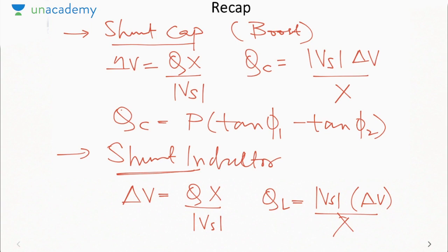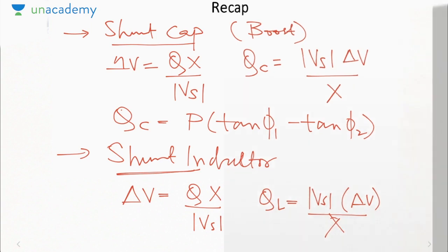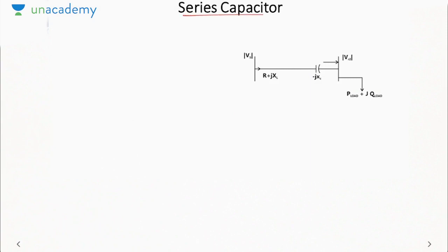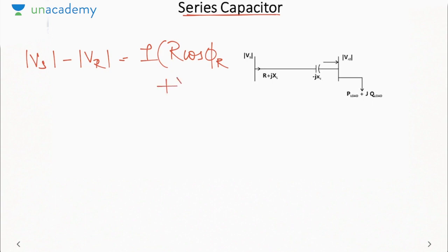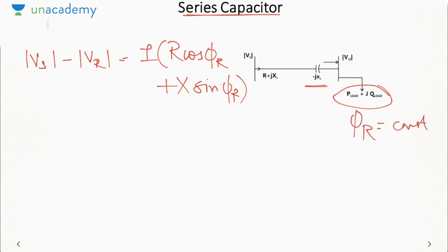In this lecture, we will see the series compensation using a capacitor. So when we talk about series capacitor, let us first see what is the voltage drop in the line. Mod Vs minus mod Vr is I R cos phi r plus X sin phi r. So here we are connecting a capacitor in series with the transmission line. The load remains constant, hence I will say phi r is constant, as well as what is constant is I am assuming current is also constant. Okay, so this is the assumption that we have made, that current remains constant, it does not change due to connection of series capacitor.